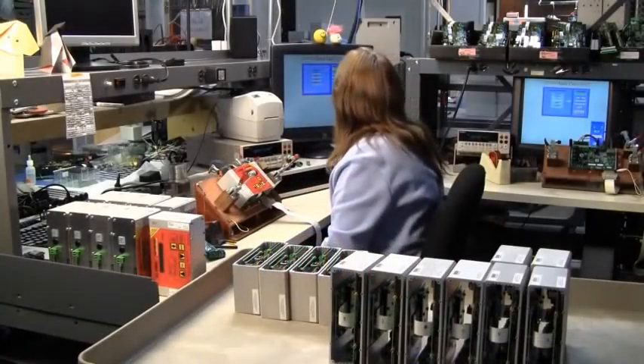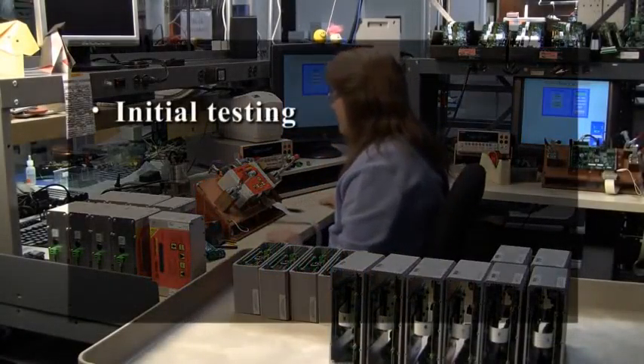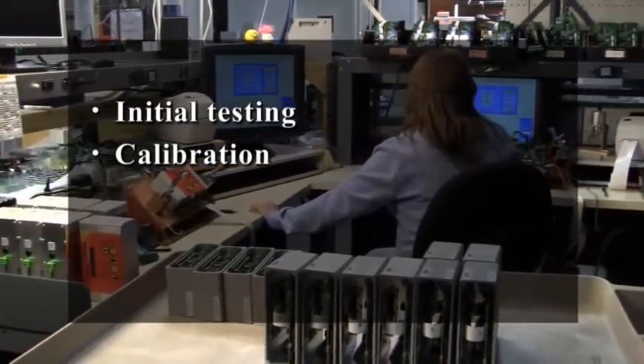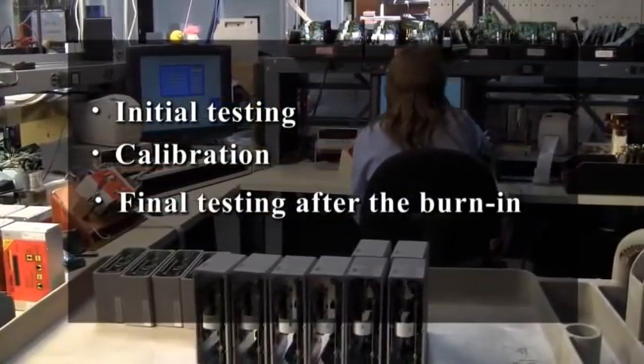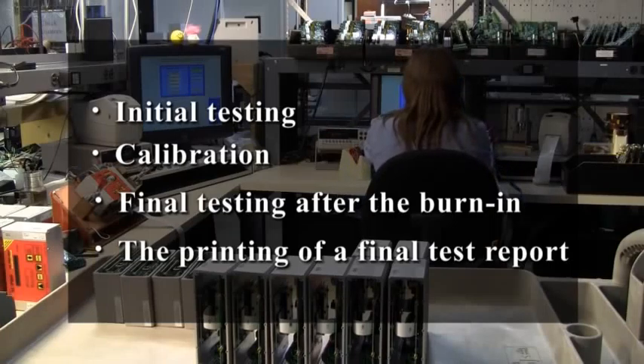The AC Pro is designed for use in rugged environments. The boards are conformal coated and it is housed in an extruded aluminum housing. We do not do any batch testing here at Utility Relay Company. Every product is tested under load at temperature for 24 hours before being approved. We've also designed a special computer-operated calibration system to test every unit. The computer-operated test system does the following: initial testing, calibration, final testing after the oven burn-in, and printing a final test report, which is included with every AC Pro.